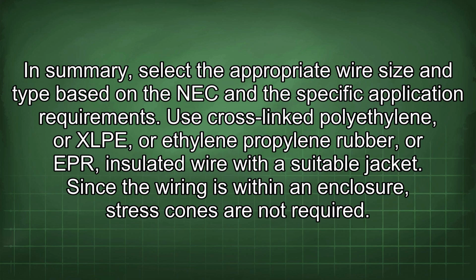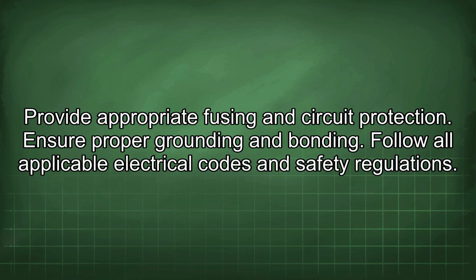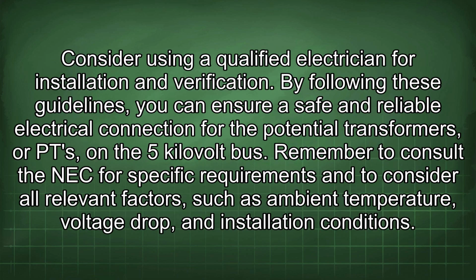In summary, select the appropriate wire size and type based on the NEC and the specific application requirements. Use cross-linked polyethylene or XLPE or ethylene propylene rubber or EPR insulated wire with a suitable jacket. Since the wiring is within an enclosure, stress cones are not required. Provide appropriate fusing and circuit protection. Ensure proper grounding and bonding. Follow all applicable electrical codes and safety regulations. Consider using a qualified electrician for installation and verification.